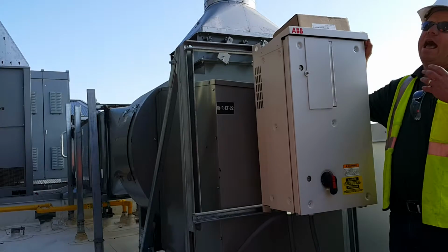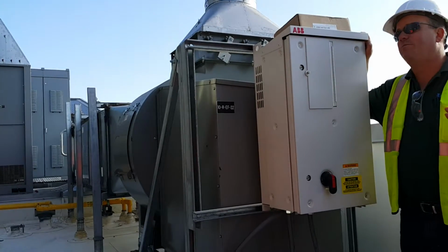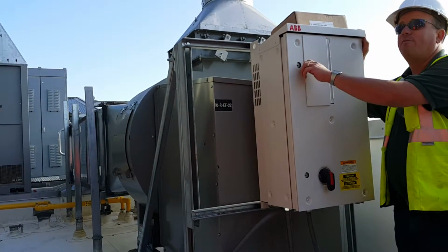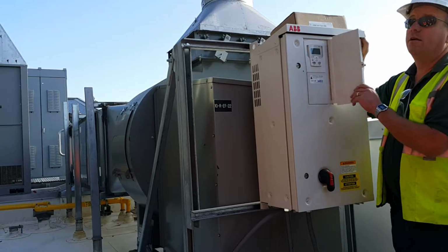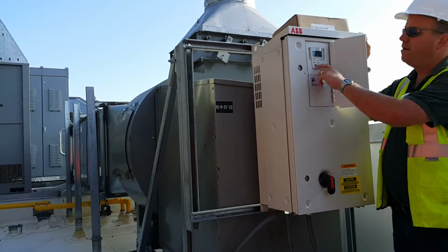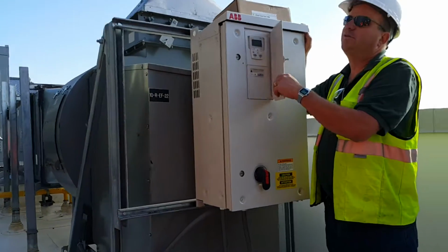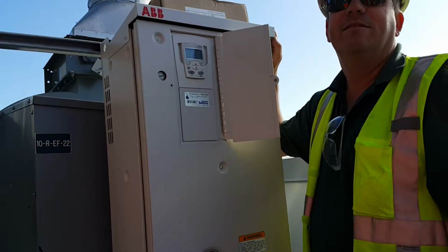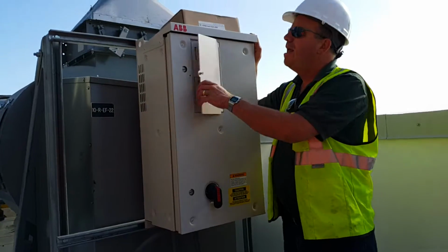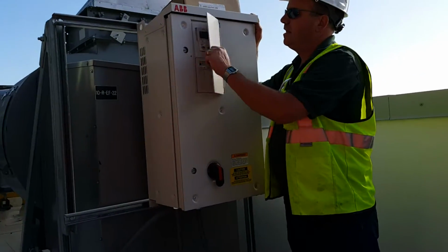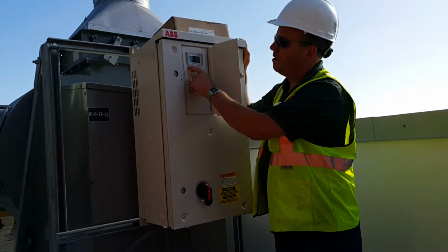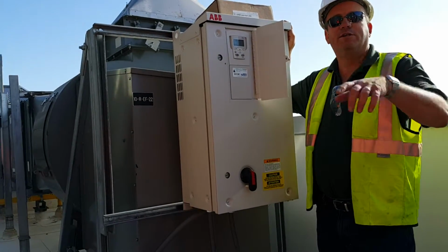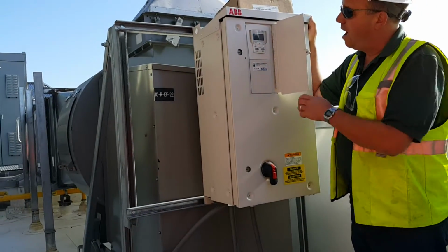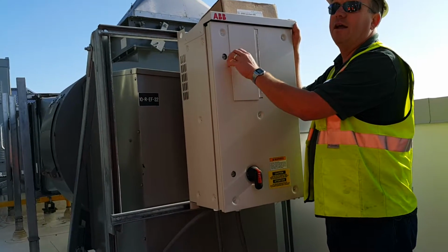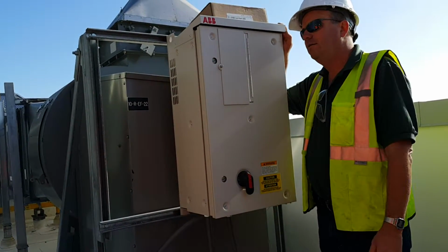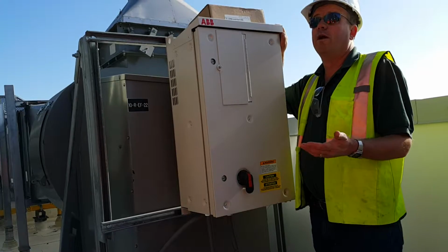You don't have to, but as a matter of habit, I've been doing this so long, I usually stop the drive before I kill it here or up there. How do you stop it? You hit the red button. That's it, right? Exactly. You don't have to ramp it down or anything. Just boom, off, and then boom, back on. Even if it's already turning, it'll catch it and just take off. I usually stop it before I kill it just because it won't record an under voltage fault.